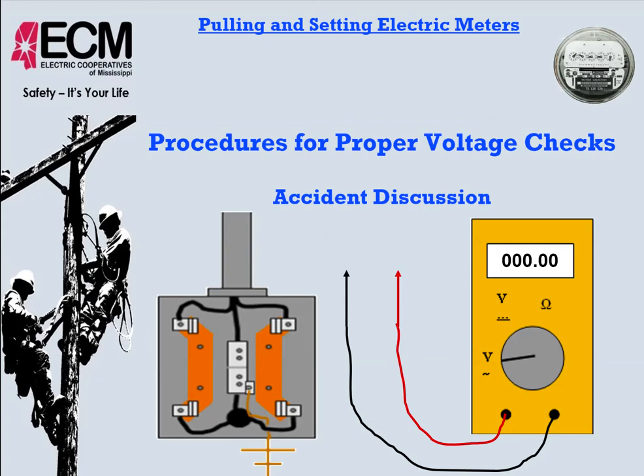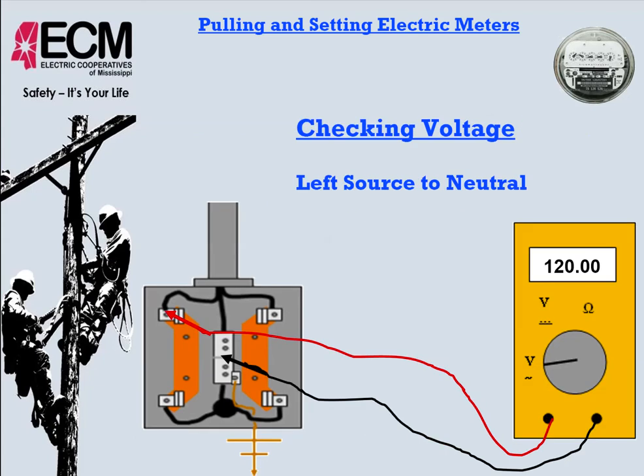So making sure that the line voltage is what it's supposed to be, where it's supposed to be, and also make sure that it matches the meter that we're fixing to set. If you're setting a 120/240 meter on a 240/480 or 277/480 meter base, that's not going to work. The meter's going to blow up. So you want to make sure that that's not happening.